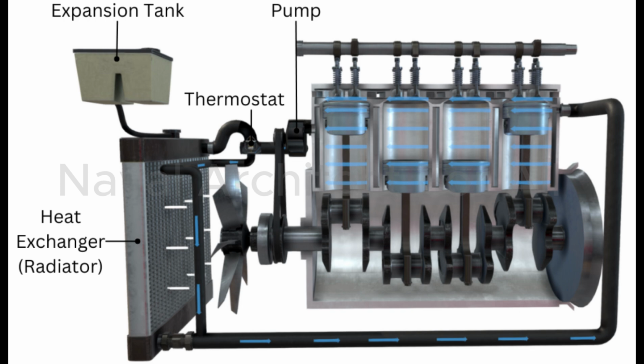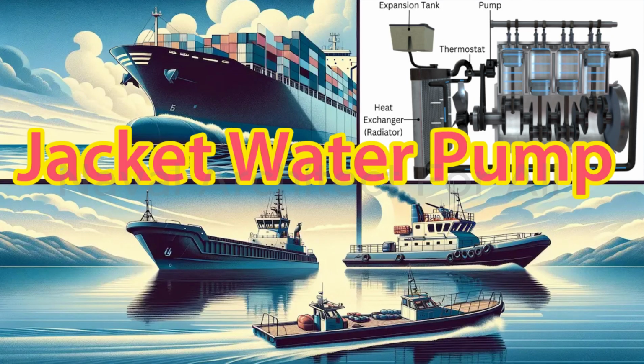Proper maintenance is crucial for reliable operation of the jacket water pump and the cooling system as a whole. Maintenance tasks include inspecting and cleaning. Regularly check for clogging in the pump and coolant pathways. Clean as necessary to maintain flow. Seal and bearing maintenance. Inspect seals and bearings to prevent leaks or mechanical failures. Coolant treatment. Use treated coolant to prevent corrosion and scaling within the cooling system.